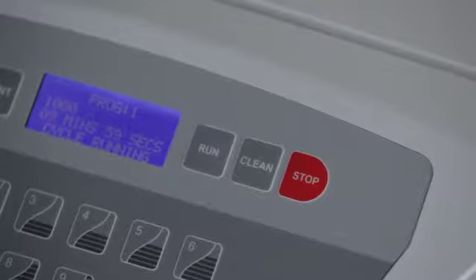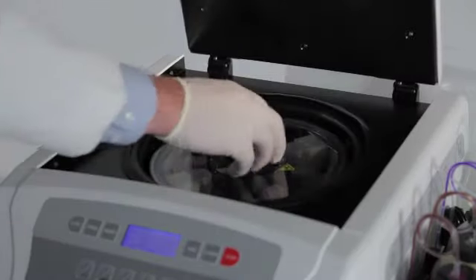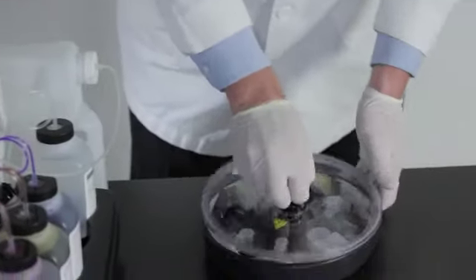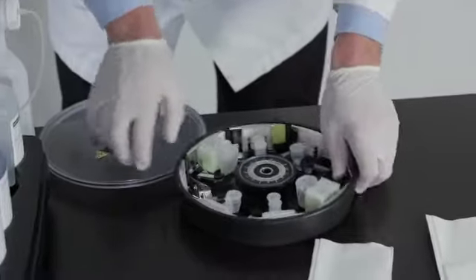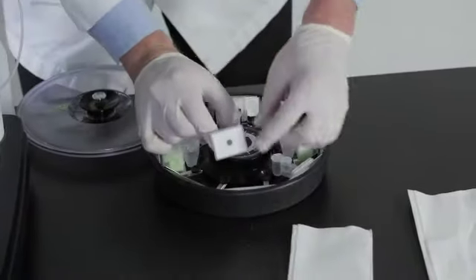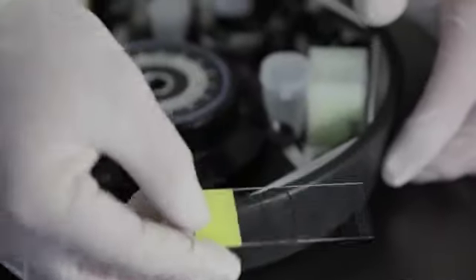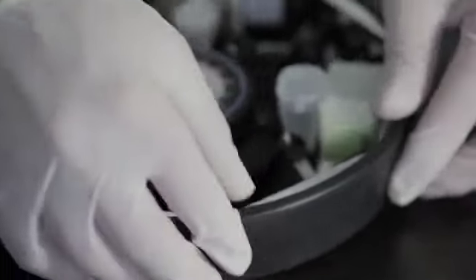The rotor will reach the set speed and spin the set time, if the lid lock delay is set to on. At the end of the cycle, users remove the rotor and remove the chambers and slides. The sample fluid is absorbed into the absorption pads in the standard volume chambers during the cytocentrifuge process. The slides should be treated according to standard operating procedures and eventually stained.